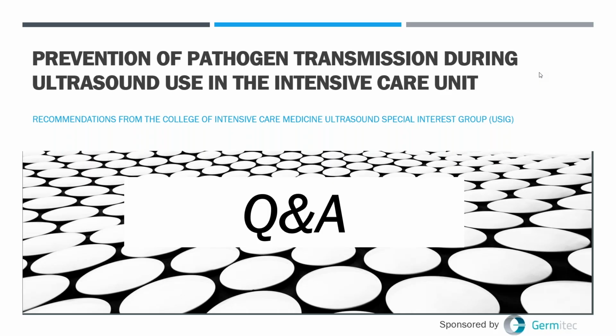Okay, thank you. We use Tegaderm as our probe cover to reduce cleaning and HLD or LLD after use based on procedure. This ensures we have a quick turnaround time. What do you use? We use sterile probe covers, yeah. So we don't recommend them. I mean, they provide an inconsistent barrier. I mean, they do probably minimize soiling, and they're not doing nothing, and they probably do increase efficiency with disinfection cleans. I think as long as you're doing a good disinfection afterwards, that's more important. But just don't overestimate the benefit that you're getting from a sterile cover.